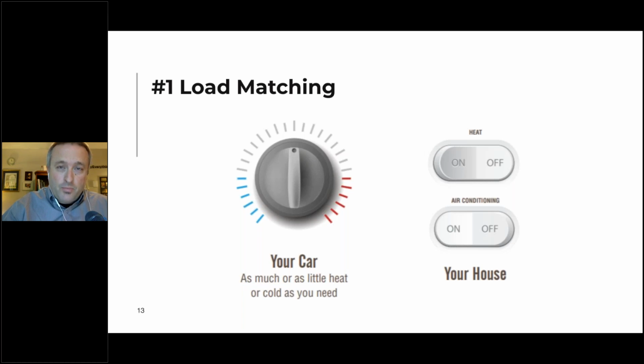In a house, you can't do that. 85% of existing HVAC systems on the market are single stage, meaning they're either on or off, so there's no real control. When it's 50 degrees outside, there's very little load, so the house doesn't need much. If your house feels cold at 50 degrees, the odds are your equipment is drastically oversized. In general we find equipment to be 2 to 4 times larger than it needs to be when we do a true load calculation based on blower door testing and energy use.